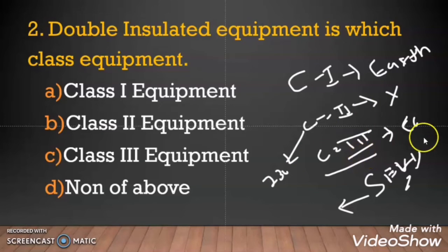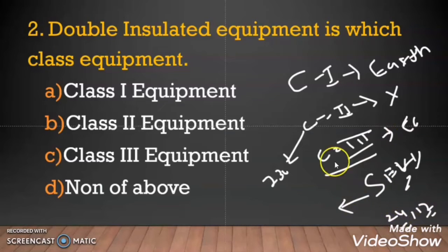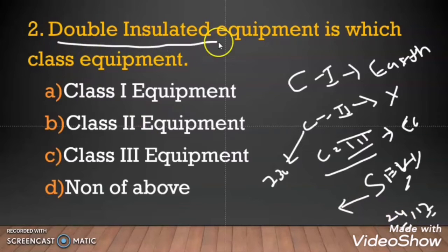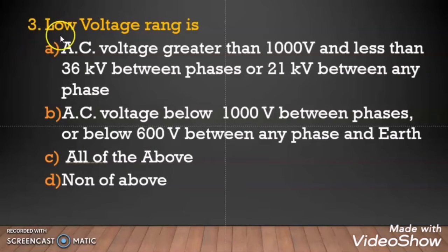Class 3 equipment works on a separated extra low voltage system, with voltage magnitude as low as 24 volt or 12 volt. At this voltage you will not get any electricity shock, so this equipment also does not require earthing. The difference is that Class 3 has very low operating voltage, while Class 2 operates at normal low voltage but with double insulation. So as I told you, the answer is Class 2 equipment.